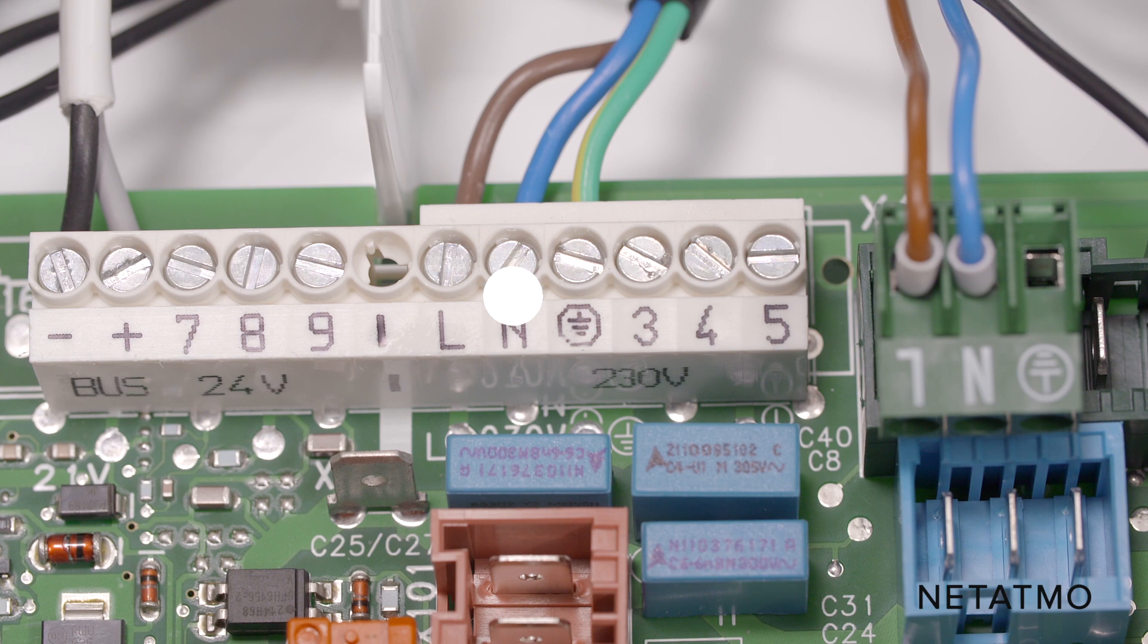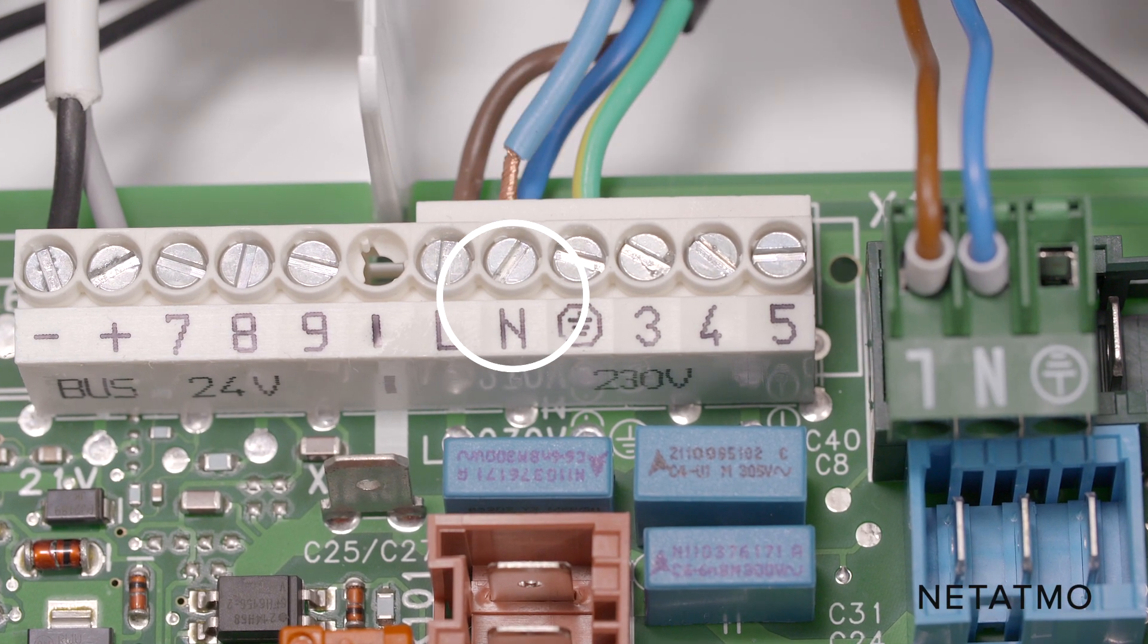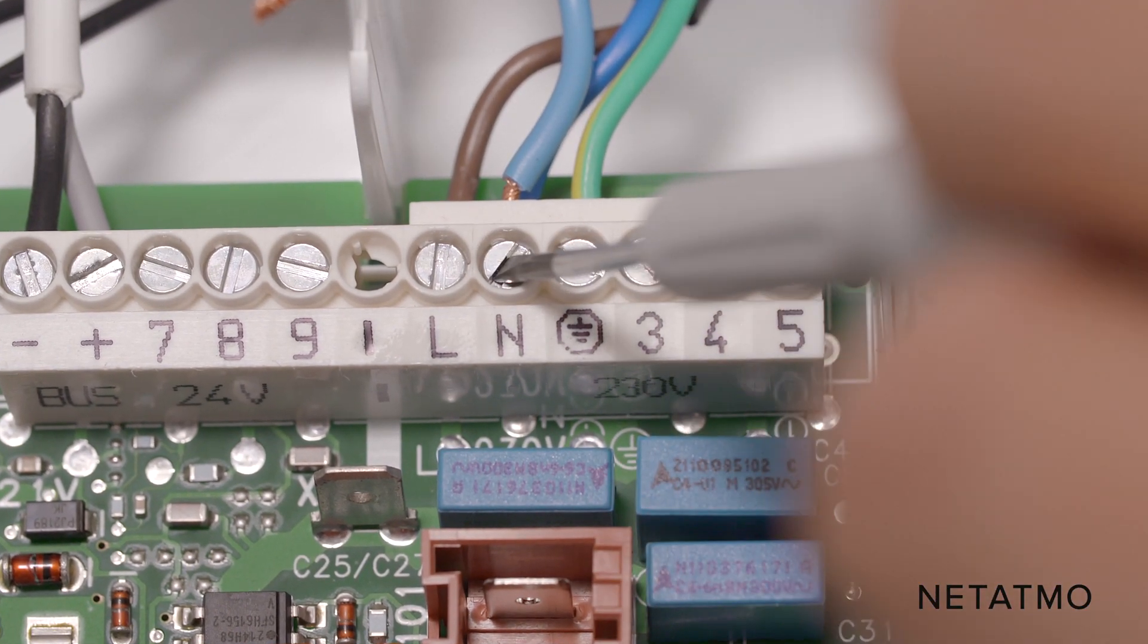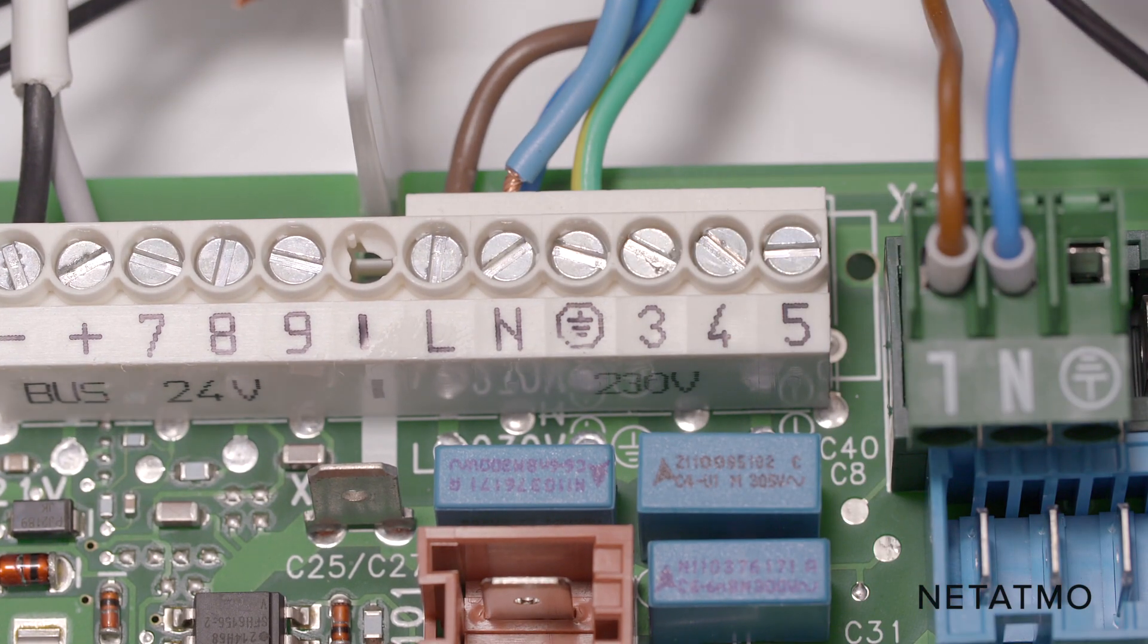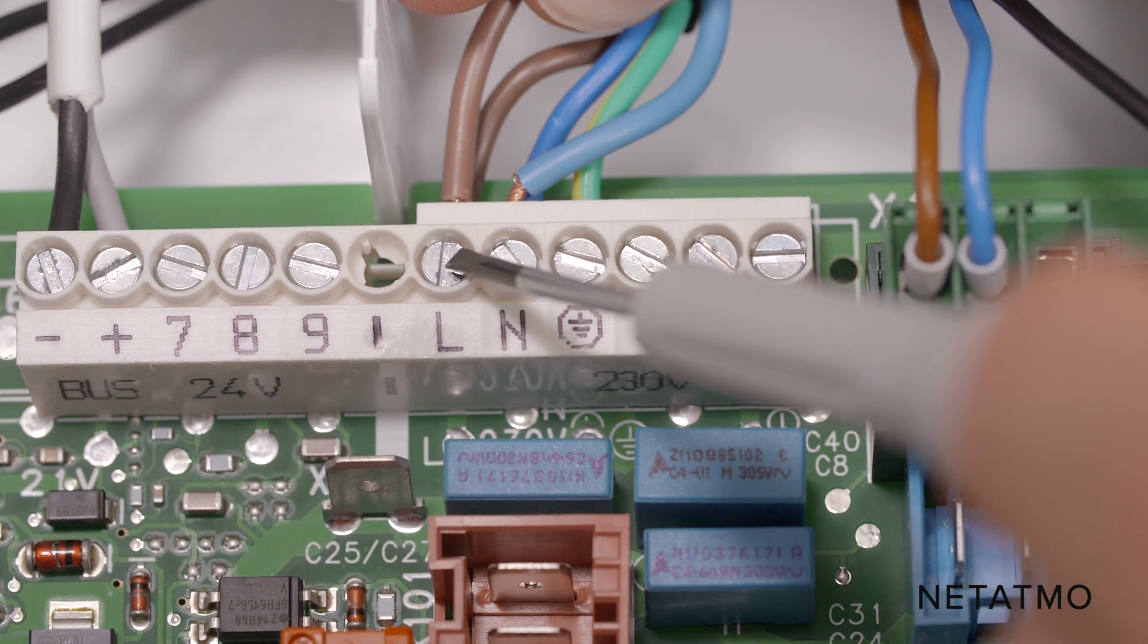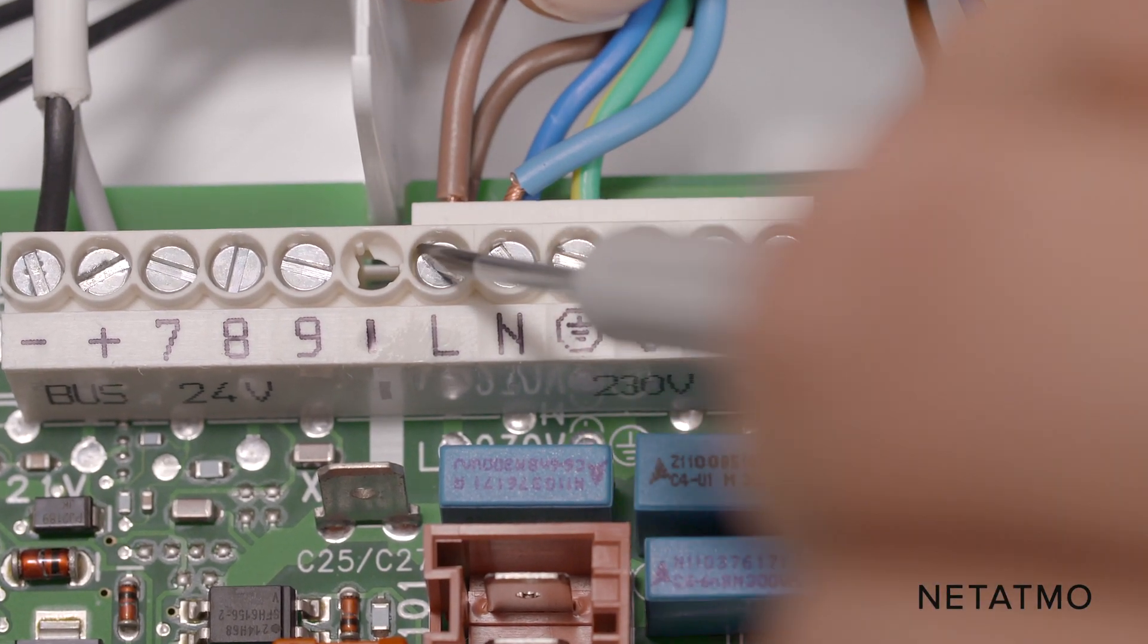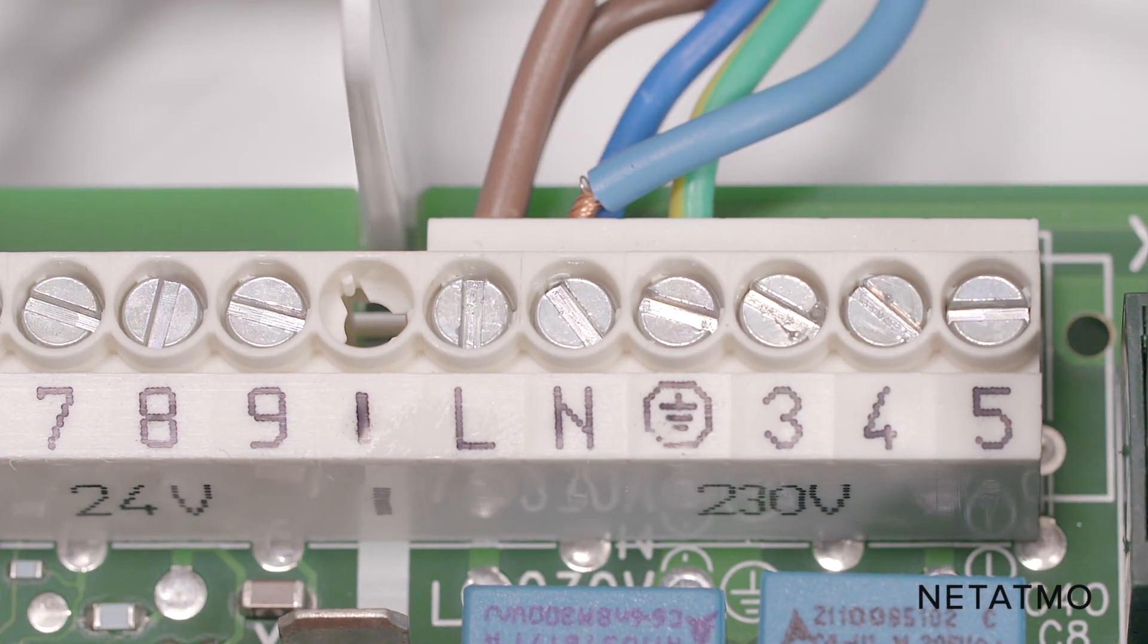Connect the blue wire of the boiler adapter to the N terminal of the boiler, where the blue power supply wire of the boiler is already connected. Connect the brown wire of the boiler adapter to the P or L terminal of the boiler, where the brown power supply wire of the boiler is already connected.